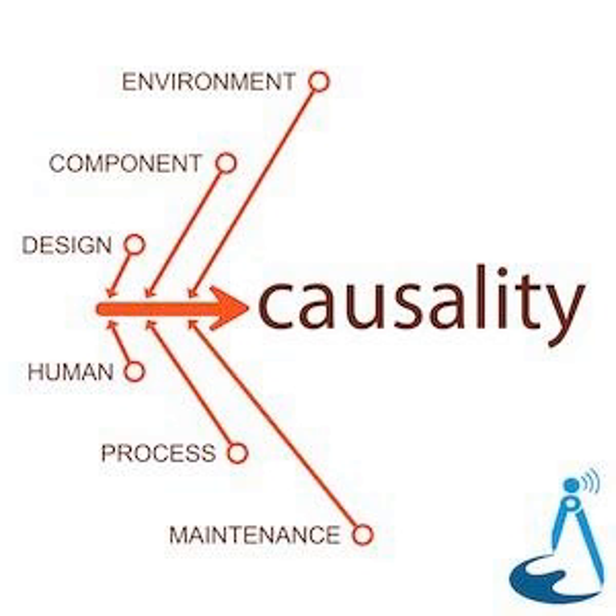Now, it had to be about something else too, didn't it? The running costs. The seawater pumps needed to lift water from the sea to cool the plant. The higher the plant is, the bigger the pumps needed to be, because they're pumping against a much higher head pressure. Lifting all that seawater a much larger distance would have much higher long-term operating costs. Maintenance costs would also be higher for the pumps, making it more expensive as a long-term operating cost. So by lowering the height, you reduce the pumping distance, which makes it cheaper.